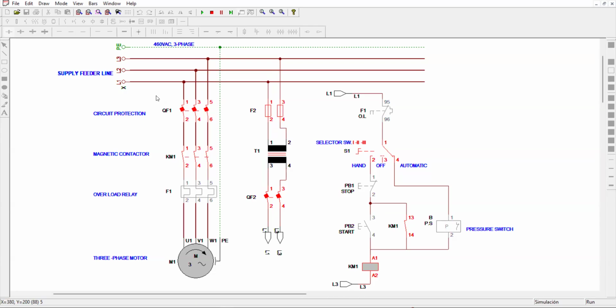So once the pressure switch is activated, the circuit will lock in, and the motor will continue to run until the preset pressure is reached. The motor can be restarted by deactivating the pressure switch. So if we select the selector in the off state, it automatically turns off. If we select it in automatic mode, the motor runs automatically. If we select the selector in manual mode, there is manual intervention with a push button here. On, off, on, off. But if we select automatic, it automatically operates this three-phase motor.